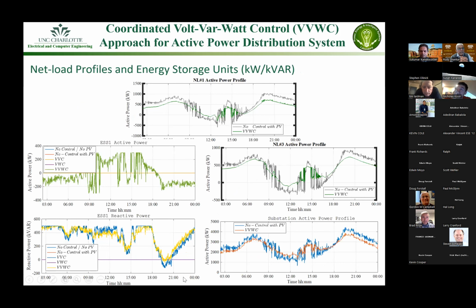Here's an example showing the effectiveness, what we call a local duck curve, similar to the aggregated duck curve seen in the EMS, but at any PCC or sub-area in the distribution system. With intermittency improvement and shifting, you can improve this duck curve, the lighter dots show less intermittency and a downward shift toward a flatter line, depending on capacity, this can even become a straight line.